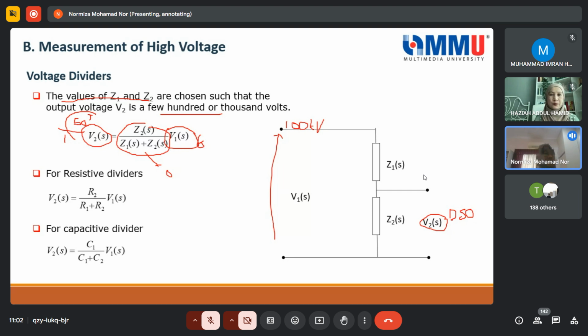V1, sorry. It means that when you get the value, then you have to divide by this value here to give you the real output. For example, how much is this, not point, not 1? What is it? When 50 divided by 100 kV, it is 0.0005. Yeah, 0.0005. Okay. So when you obtain this voltage at the oscilloscope, then you have to divide by this. Then you get V1, how much is actually the real voltage applied to the test load.